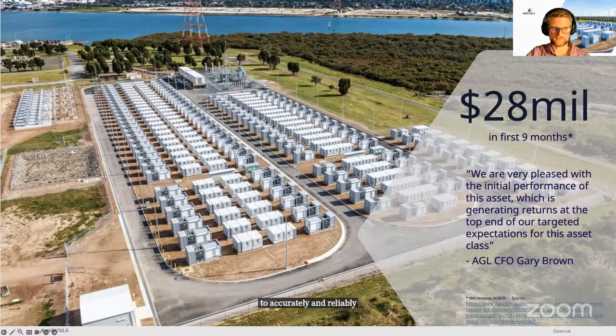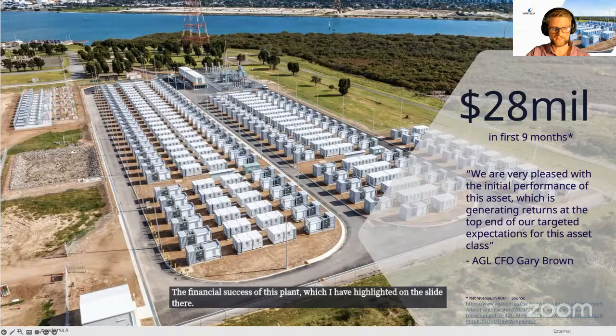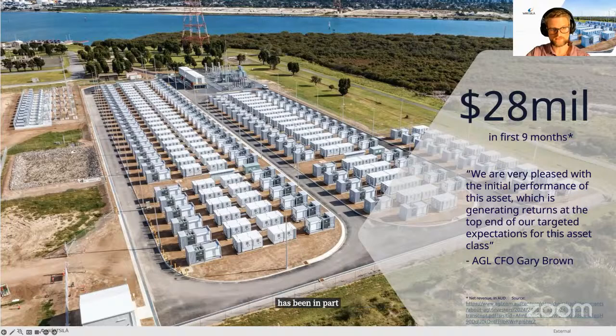The PPC must leverage high-speed measurements, closed-loop controls, and efficient power allocation to accurately and reliably respond to these grid disturbances. The financial success of this plant, highlighted on the slide, has been in part driven by this very fast FCAS, specifically the RAISE market, where you're exporting power, with this one plant providing about 15% of the total national demand for this service in Australia.